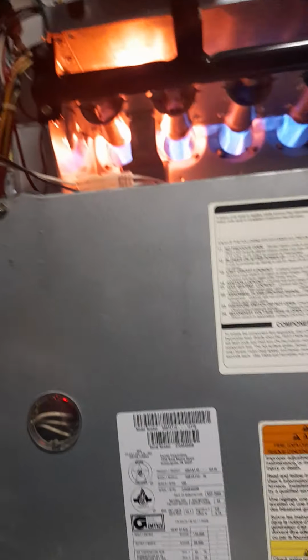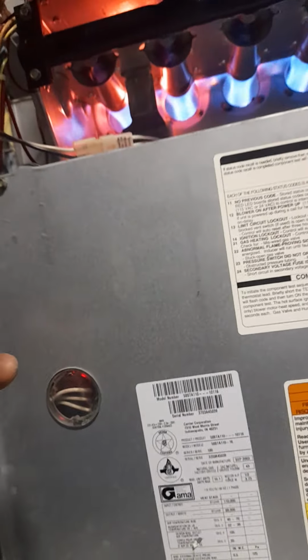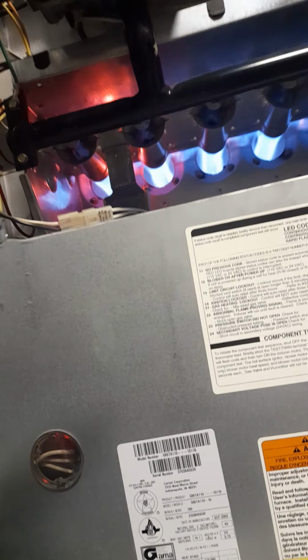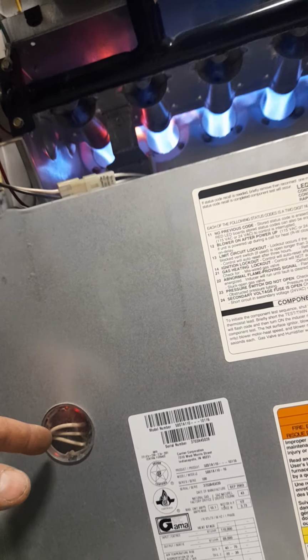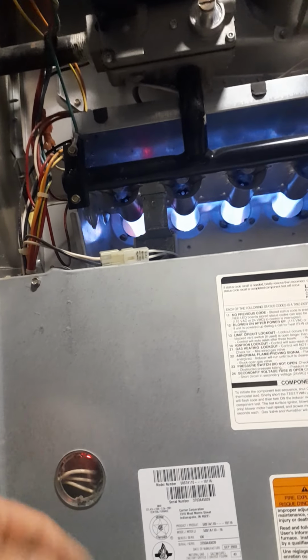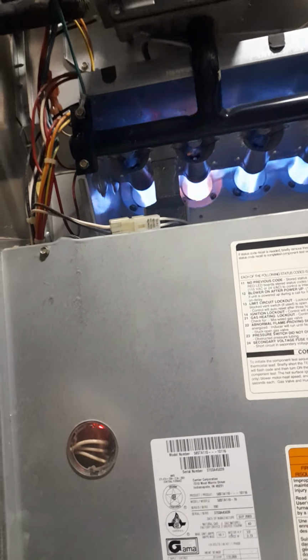That detects flame. There's usually another light on these boards, like an amber light that shows it's detecting flame. That's how you know your flame sensor is dirty, because you'll see the burners go out right after the amber light disappeared. But no one ever looks through these. I didn't even know it existed.